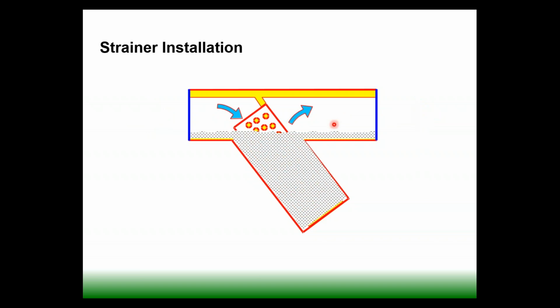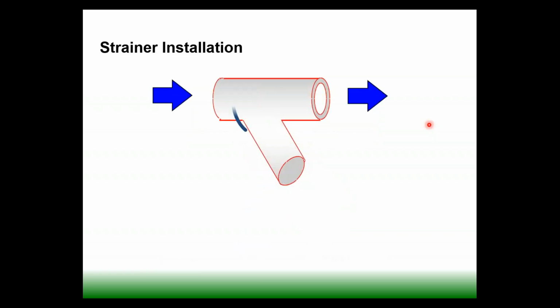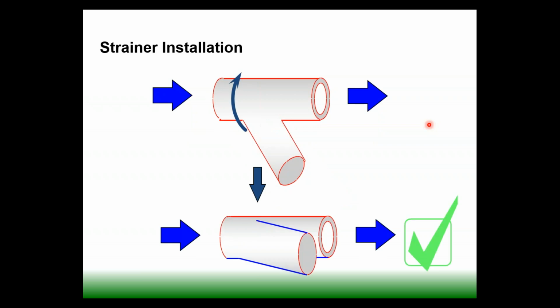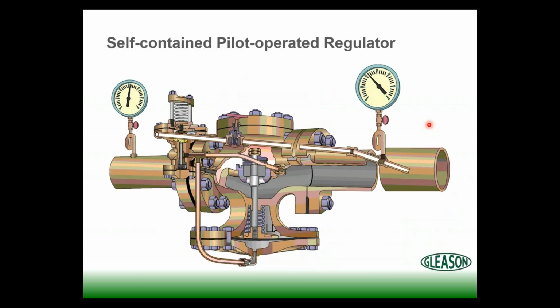Well, what else collects there? Water collects there. And so when that control valve downstream opens up, it will pick up some of this condensate off of this portion of the strainer. And then two things will happen that will negatively affect the regulator control valve. As it goes through the valve seats, it will wire draw. Actually, it can cut the seats if we're pulling water along with our steam. And secondly, as a percentage of that very, very hot condensate flashes across those seats, it can damage the seats as well. So we want to rotate the strainer to where the screen portion is in the horizontal plane, and that will far extend the life, definitely help extend the life of your regulator's control valves.